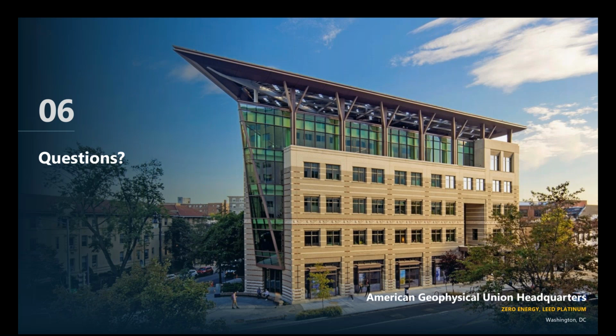There's a question about whether performance diminishes over time. That's a great question, and it goes back to optimizing the design and taking advantage of the full bandwidth of the field. If you don't optimize during design and don't account for the 30-plus year performance of the field, you can find that it diminishes over time. But as part of designing a geothermal bore field, that's one of the things we focus on - making sure we get stable operation year in and year out, so the system works appropriately in the future.